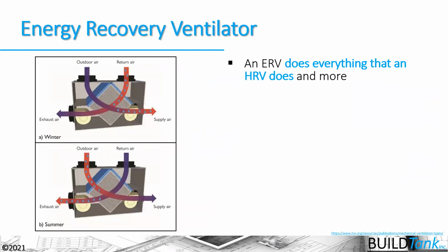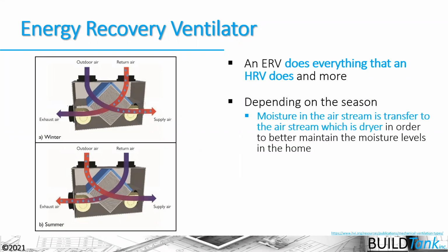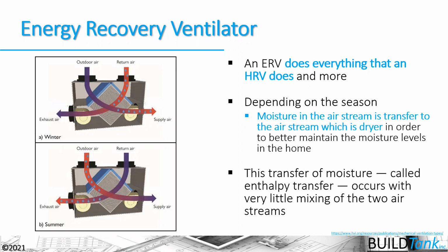Energy recovery ventilators basically do exactly what a heat recovery ventilator does, except that, depending on the season, it has the ability to move moisture in an airstream to a different airstream. That movement is based on moisture content. Again, moisture moves from higher concentrations to lower concentrations. So let's say in the wintertime, in Colorado, I have more moisture inside my house than outside. The exhaust air is going to transfer some of its moisture to the incoming drier fresh air coming into that house. So I can keep control and predictability not only of the airflow, but of the moisture content inside that house as well. So we're able to transfer heat and moisture with an energy recovery ventilator here.